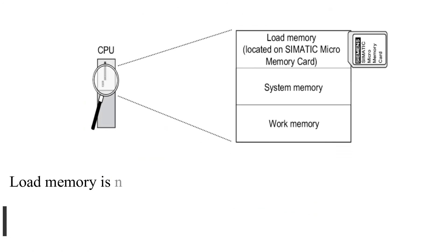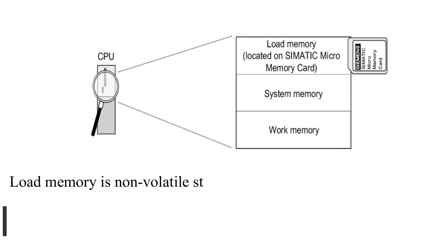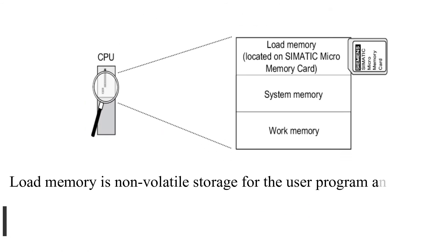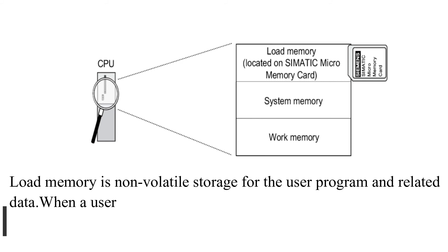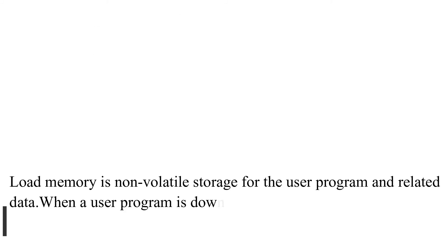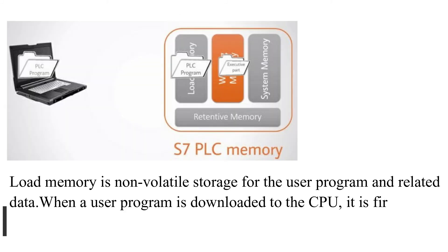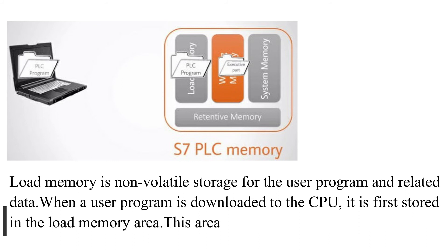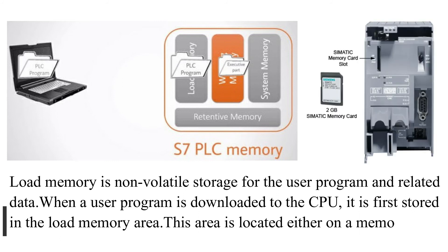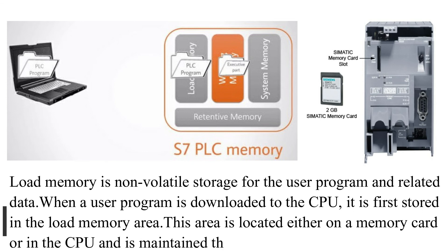Load memory is non-volatile storage for the user program and related data. When a user program is downloaded to the CPU, it is first stored in the load memory area. This area is located either on a memory card or in the CPU and is maintained through a power loss.